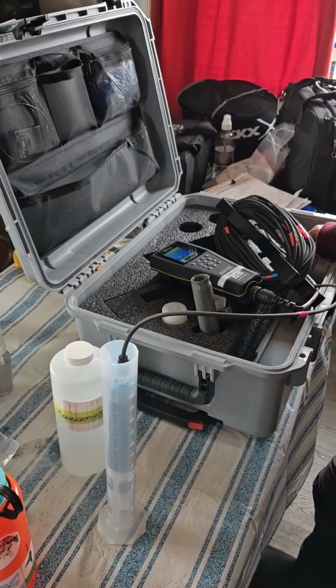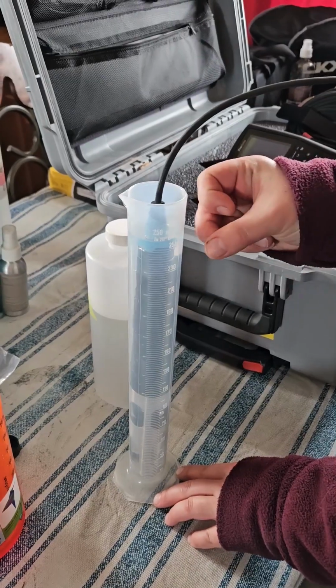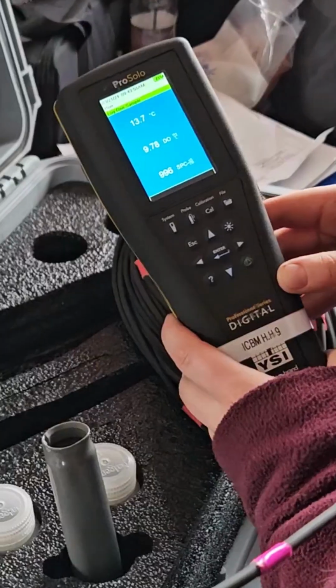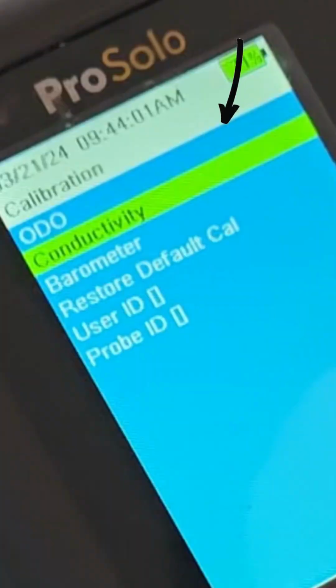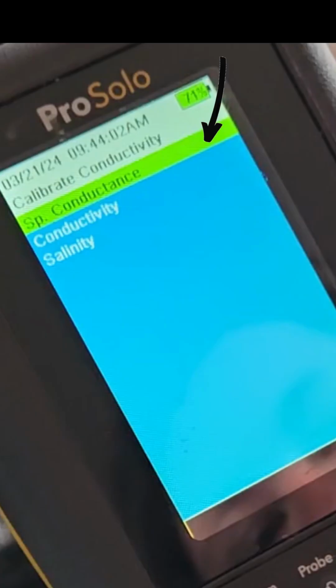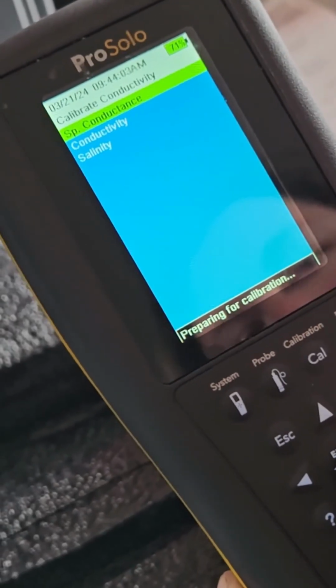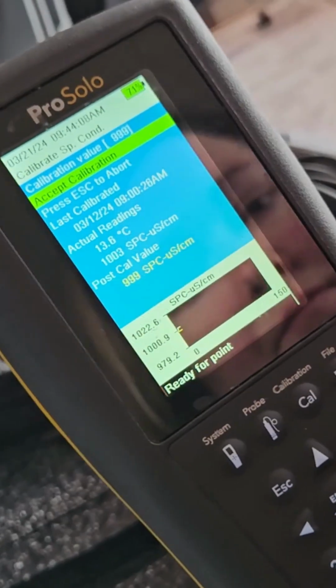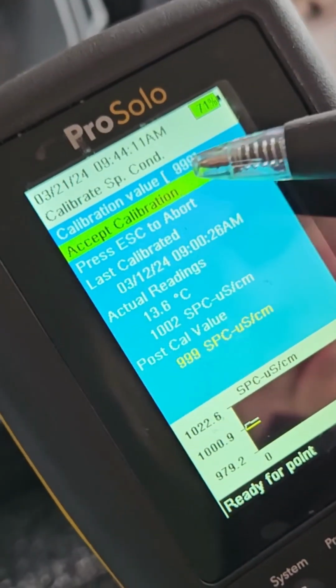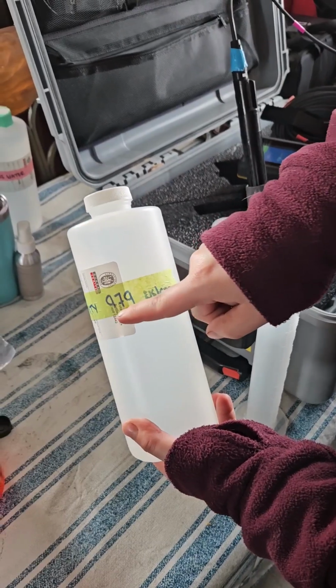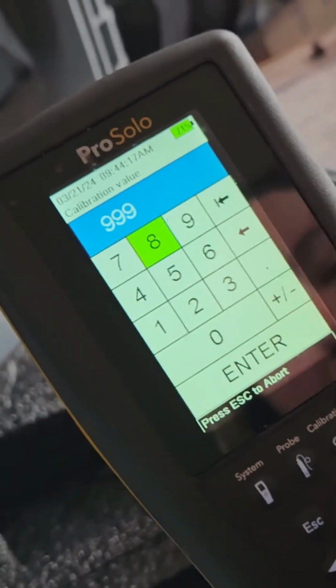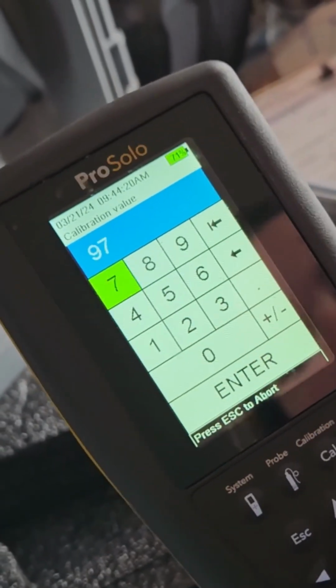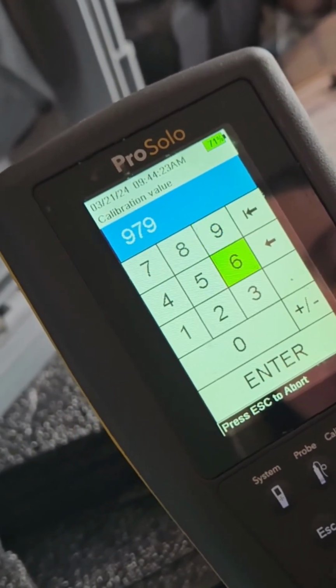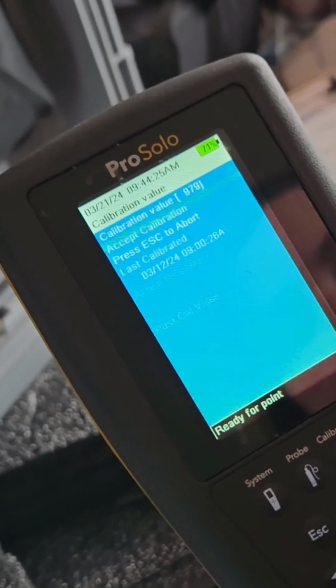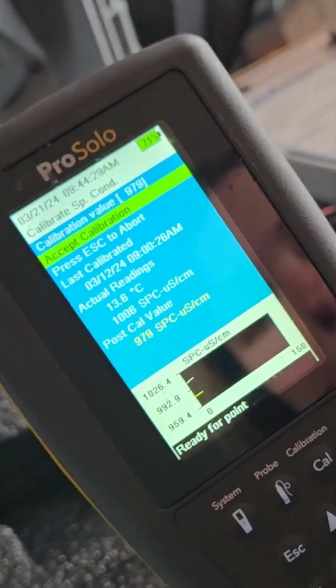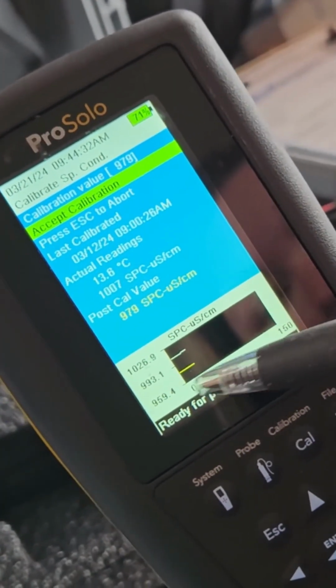Once that's completed and we're making sure that there's no air bubbles, we will go to our handheld and press calibration, this time looking for conductivity, enter. We'll click on specific conductance, and then we will be at our screen again, and we will click on the calibration value, and we're going to change that to those numbers that are written on the calibration solution bottle. So for here, it's 979. We'll enter, and then we'll see that calibration is beginning. We're seeing those lines go across, and we will let that sit for about a minute.